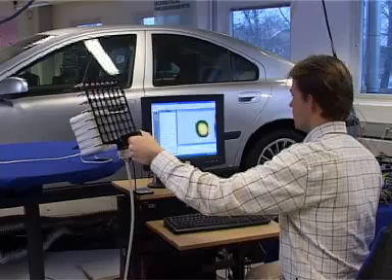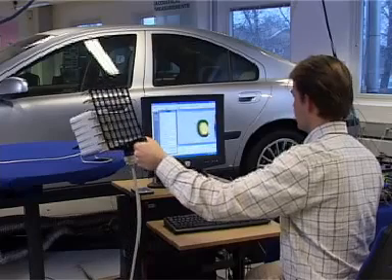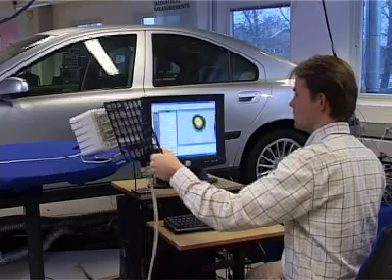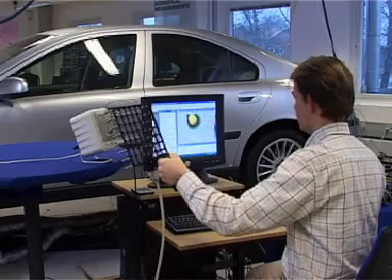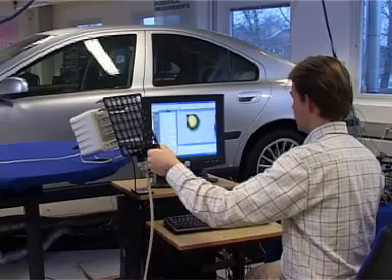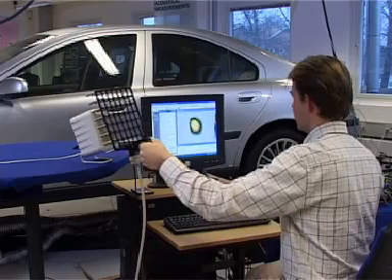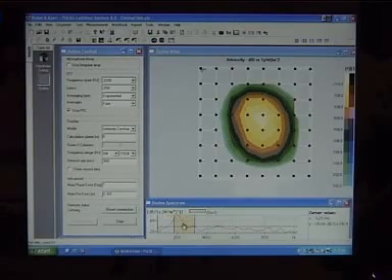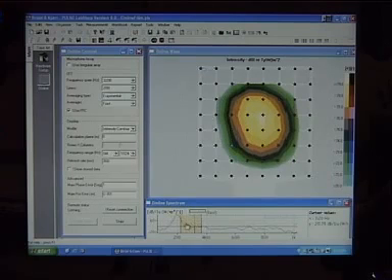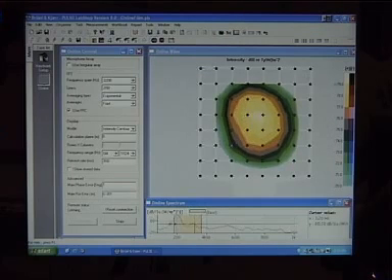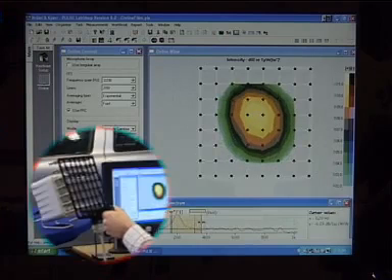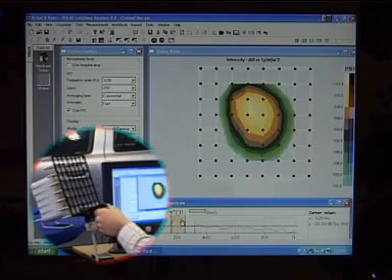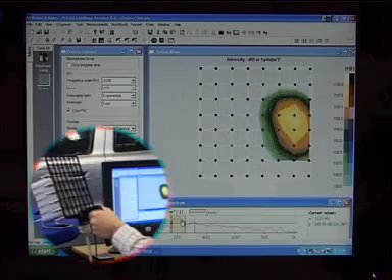During the measurement, the system continuously maps the sound intensity component orthogonal to the measurement plane. This is computed by repeatedly using acoustical holography on short time blocks. The frequency band mapped may be adjusted to match the observations being made. A special adaptation of holography is used to avoid the edge effect that would usually be seen when major sources are outside the measurement area.